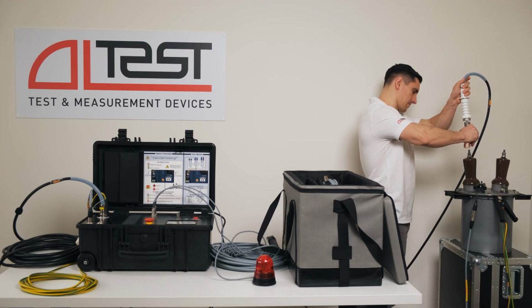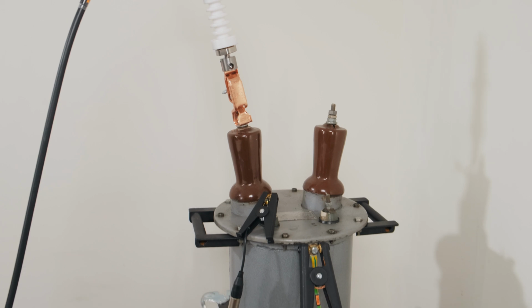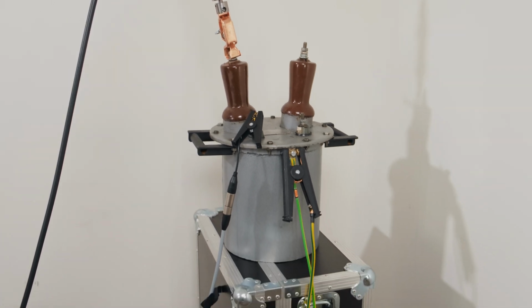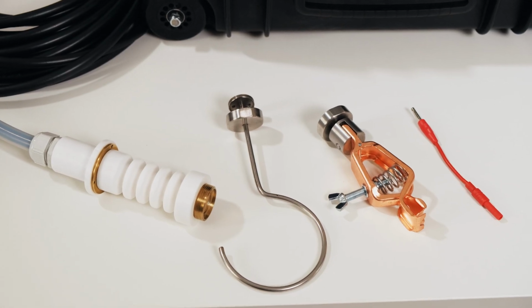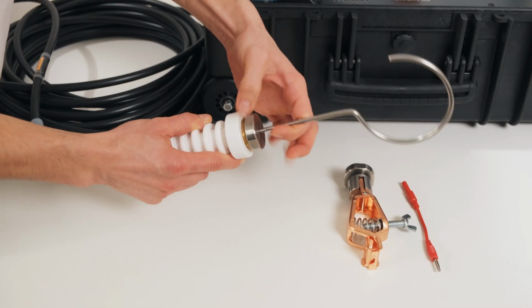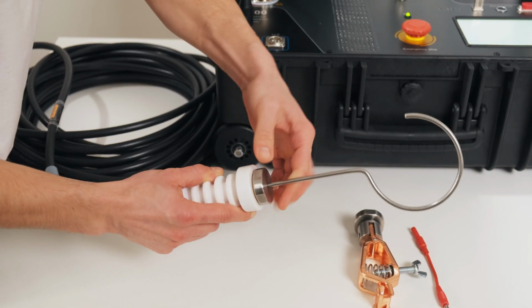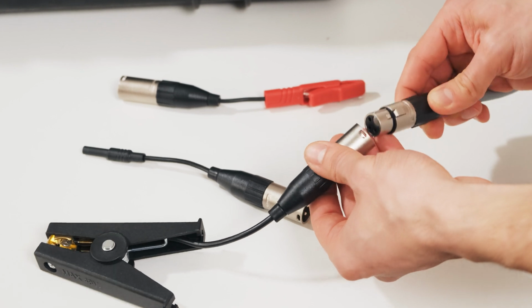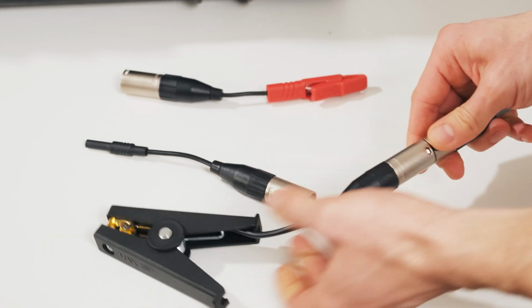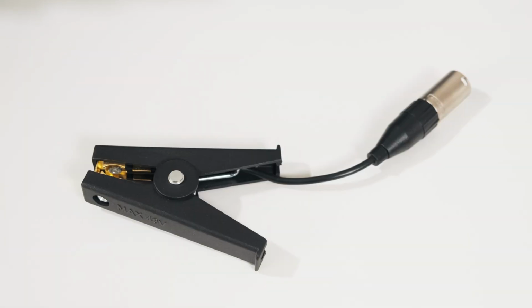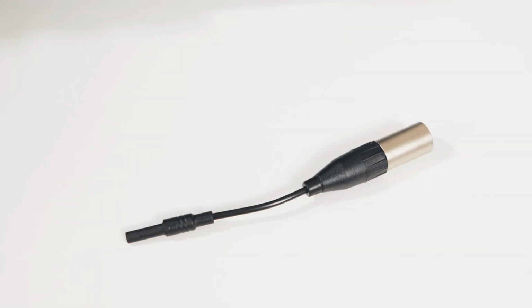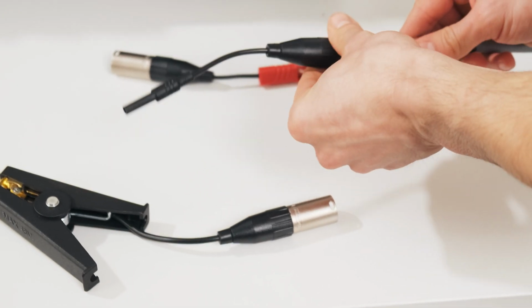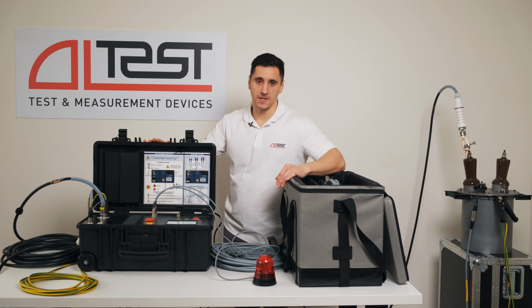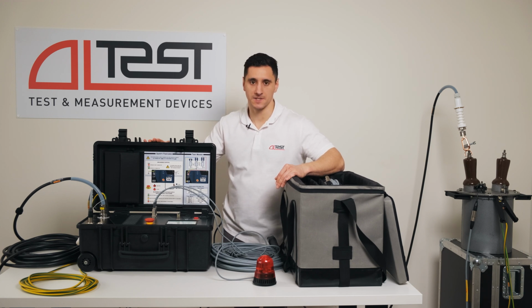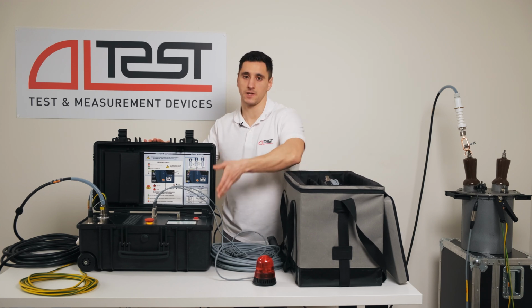Let's connect the cables to the measuring object. In our case, it is a voltage transformer. High-voltage cables can be connected with a hook or clamp tips. You can use various tips with the measuring cable: a small clamp, a large clamp, and an adapter for connecting to the bushing tab. The test process is controlled directly from the touch screen located on the main panel of the D100.